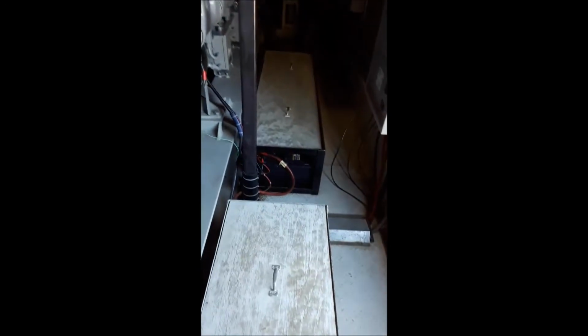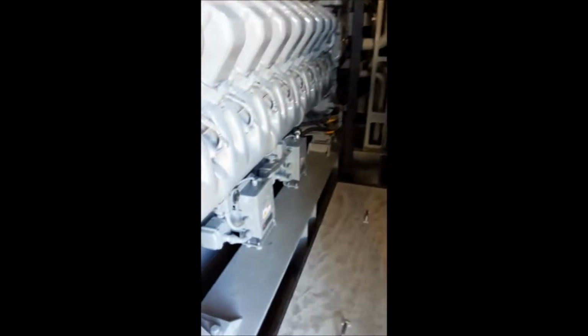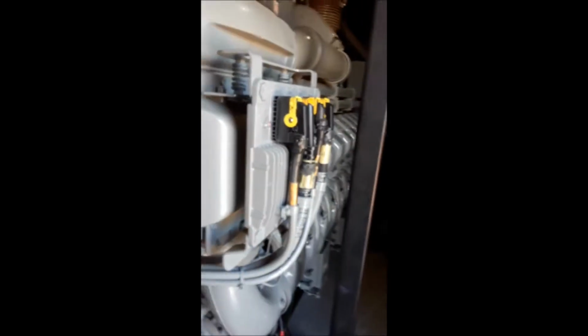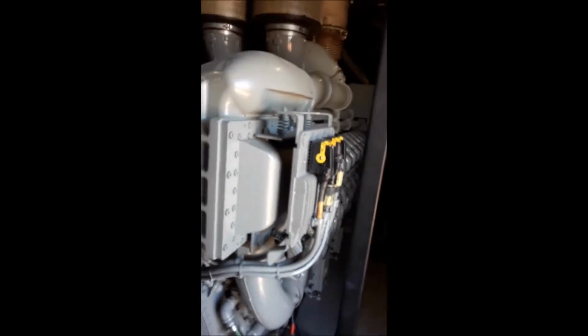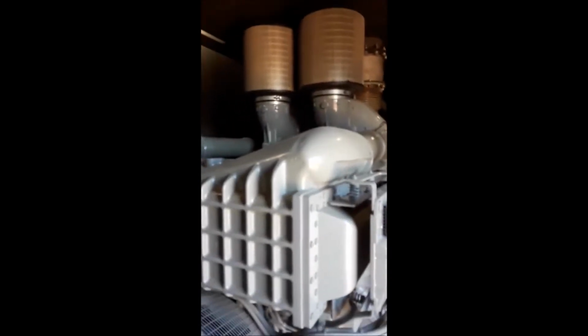Everything's redundant. There's dual sets of batteries, dual starters, dual battery chargers. There's jacket water heaters, because they start and go right to 1,800 RPM. There's no warm up.